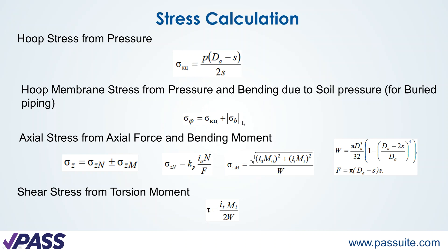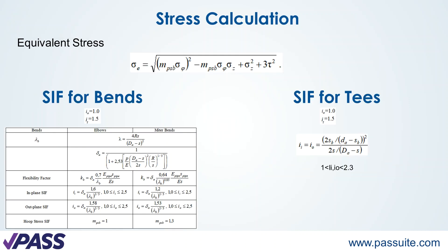The bending stress is added from the soil pressure if the plastic pipe is buried underground. The axial stress from bending moment and axial force is calculated by this equation, and special stress intensification factors are applied. This is the shear stress from torsion moment, and the equivalent stress is calculated by this equation.